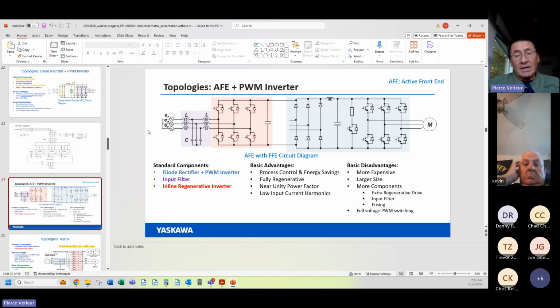Again, a huge energy savings, right? A hoist, an elevator, an escalator becomes effectively parasitic power consumption. What you lift must go down. What goes up must come down. And when it comes down, you put the power back into the line, less the operating inefficiencies. So very, very important development. However, this is not new technology. This is basically 1983 regurgitated.